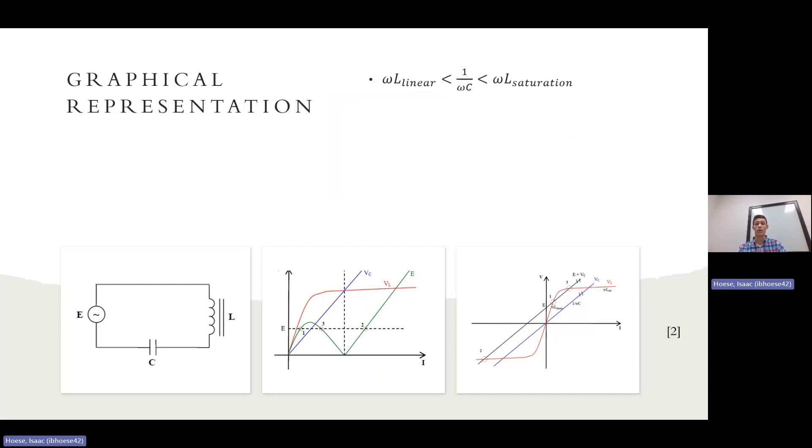Point two is when the capacitor voltage is greater than the inductor voltage. This is also considered stable because it's away from the knee region, but it's a stable ferroresonance state. So it is under ferroresonance, but if it's in this state only, then it is considered stable. And point three is when the inductive and capacitive reactances are equal, thus creating a very, very low impedance circuit. This is where our over voltages and overcurrents are going to occur.